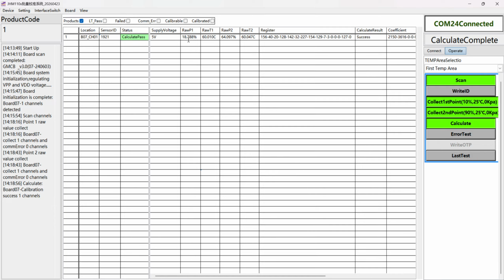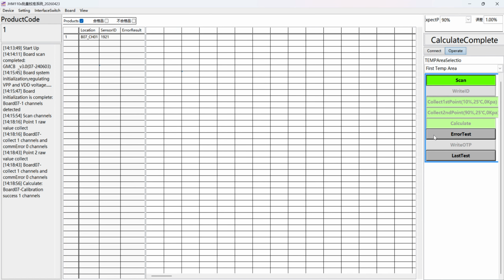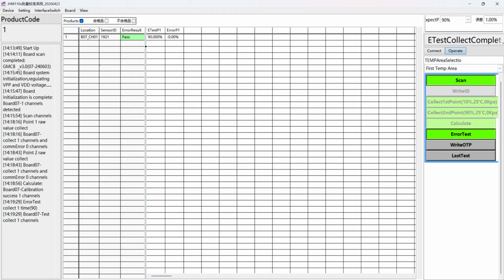Okay, the calculation passed. It's collected, and I will do the error test. I click the error test, and the screen will change to the error test screen. Here is the error test. Here we can see this is 90%, and 90% is the full point. So here my transducer is already at the full point, so I click error test. 90% is okay. And then I change the transducer to 0 point, and I change the expected value to 10%. And I also click the error test.